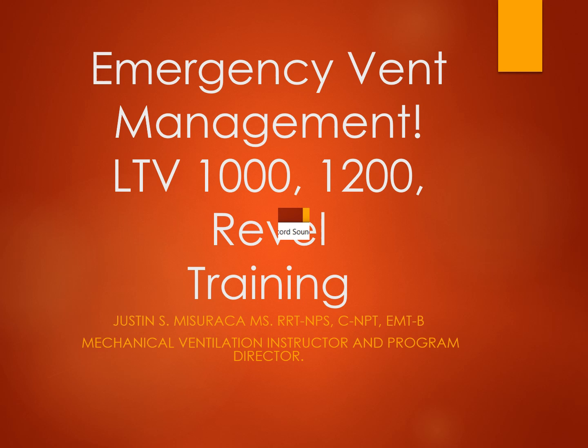And make sure that you're pressing that little button on the side that says low O2 source. If you don't press that, it doesn't know that you're switching over to 50 psi, and it's going to be pretty mad at you the whole time, and it's going to start yelling at you. And if you haven't read your manual and don't know what that means, you are going to look like a fool with all that beeping and screaming.